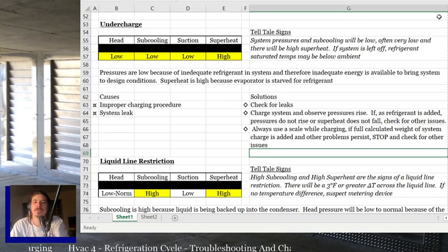But anytime I charge a system, and I think it's a pretty good habit, anytime you're charging a system, just go ahead and pull out a scale. Throw the cylinder on the scale, charge the system, and watch for everything to become normal. Look at the side of the system and see what the condenser calls for. I don't even care if you calculate line set. Unless you've got a 150-foot line set, odds are if you just weigh in condenser charge, you'll get close enough that things should start looking normal.